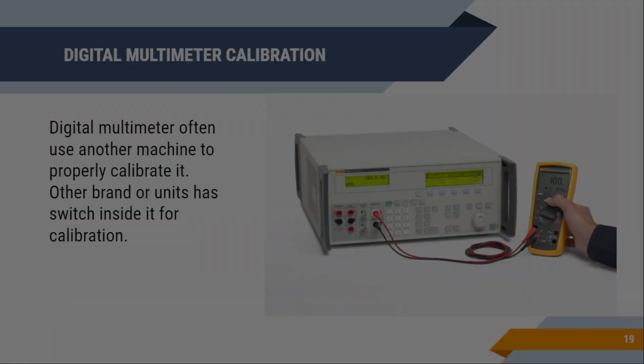Next, the significance of calibrating. Why is it important to calibrate it? An analog type multimeter is required to be calibrated every time before it's used, while digital variants are often calibrated yearly. Quality measurements and processes depend on the continual proper operation of a multimeter. However, time, environment, and physical use or abuse cause changes in the multimeter's characteristics. That's why it's important to periodically calibrate or verify the performance of a multimeter. It depends on how you use it, whether you use it frequently or sometimes you drop it, which will change the multimeter's state. If that happens, maybe your multimeter is off or has a weak battery, then it needs to be calibrated. That's what you need to do if you have some multimeter issues.